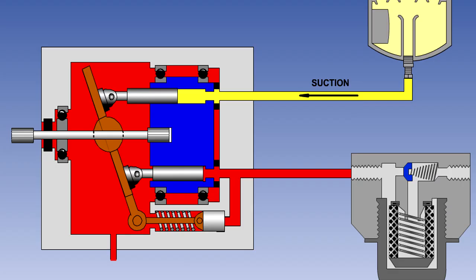When a hydraulic pump is operating, as well as supplying pressure at its outlet, it also sucks fluid in at its inlet. This suction causes a big drop in the pressure of the fluid and can lead to low temperature boiling and the formation of bubbles. When these bubbles pass through to the pressure side of the pump, they then implode with great force. This is known as cavitation, and if allowed to happen, it can cause severe damage to the pump. The sound of pumps operating while cavitating can range from a low-pitched steady knocking sound, like on a door, to a high-pitched and random crackling, similar to a metallic impact.